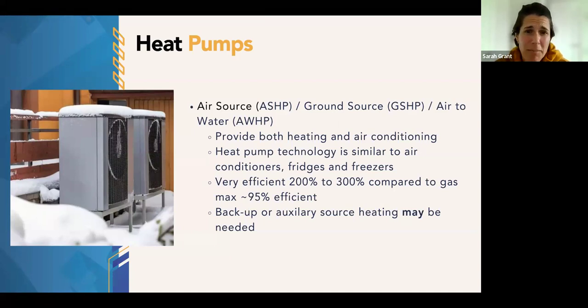We've got a few different types of heat pumps. I've been describing an air source heat pump, where it grabs warmth from the outdoor air - that's the picture there - and it may bring in that air and circulate it through your ductwork, forced air style. So you'd replace your gas furnace and air conditioner with an air source heat pump, or maybe you have cast iron radiators or in-floor heating through a hydronic source of heating. Then there are air to water heat pumps - not yet as common, and unfortunately not as many contractors are familiar with them, but they are possible. Sometimes only recommended if you've done enough work on your building envelope, since the water temperature won't be as hot as what your boiler would have produced. But it is happening in old Toronto homes.